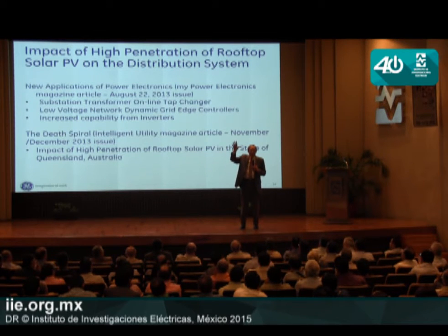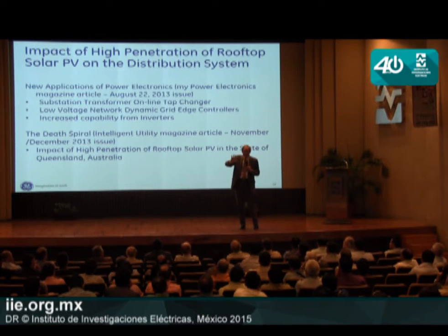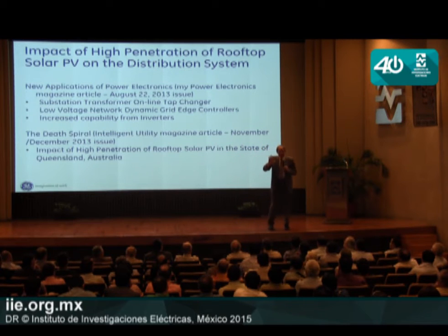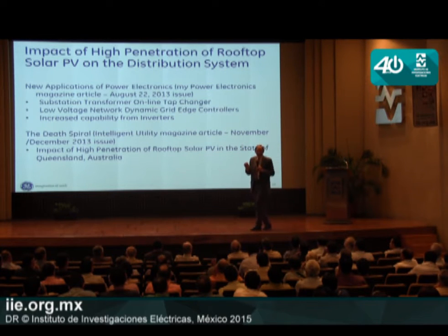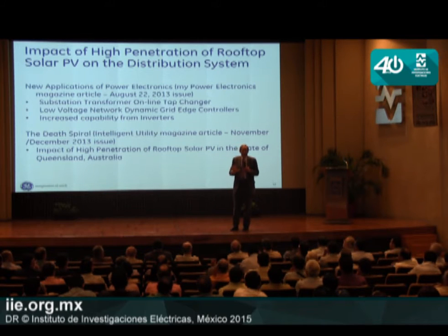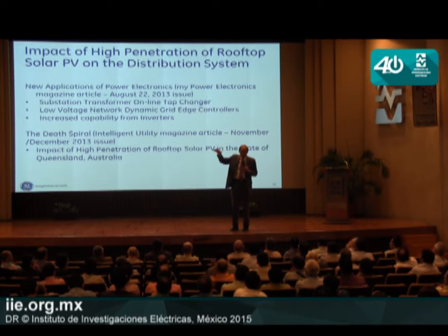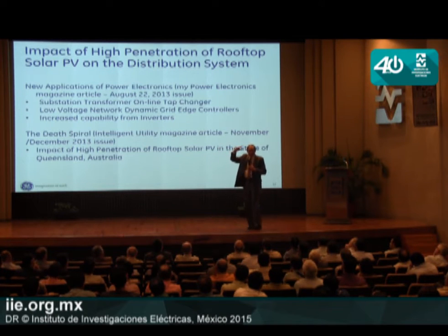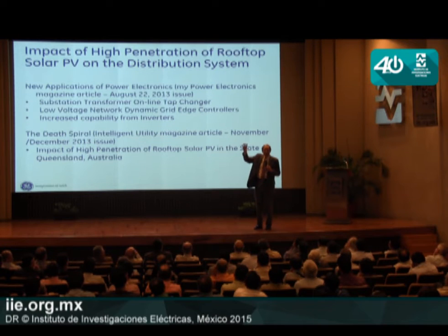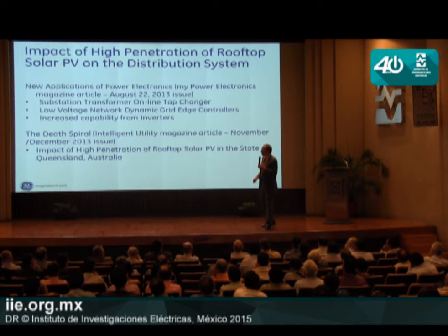In the morning, there's a marine layer of fog from the ocean that completely blocks the sun from the homes. But as the morning goes on, the fog burns off, and all of a sudden all those homes go from 0% sun to 100% sun instantaneously. What happens to the voltage on that feeder when you have over 35% penetration? The voltage spikes, and as clouds go in and out, it oscillates over a pretty wide band. At the beginning of this article I have the actual voltage waveforms from this feeder, and you can see the volatility.